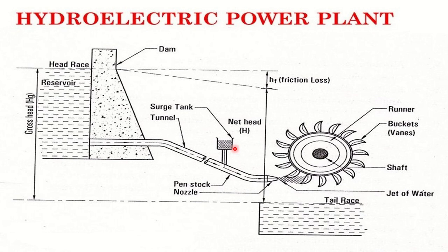Okay, it's like an intermediate storage system. It's also called a surge drum or surge pool. There you can store the water. That's one purpose. And the second purpose is that, suppose after the water enters the penstock there is any technical problem at the inlet of the turbine such that your turbine is not working. The water is already inside the penstock, so you can't send it back into the storage system. Then what we will do is store this water inside a surge tank.